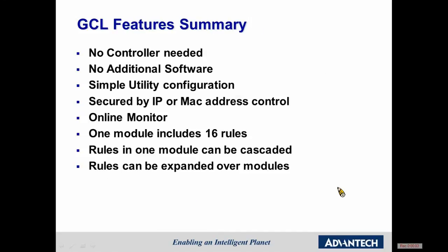So as a summary, the GCL allows you to have no controller, no additional software. It's a simple utility. It's secured by IP or MAC address. You can monitor the GCL. One module includes 16 rules, and the rules can be cascaded and can be expanded over other modules.